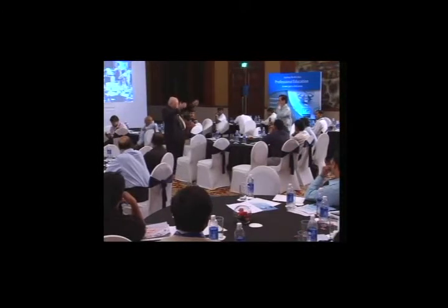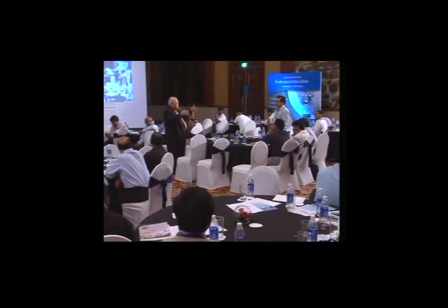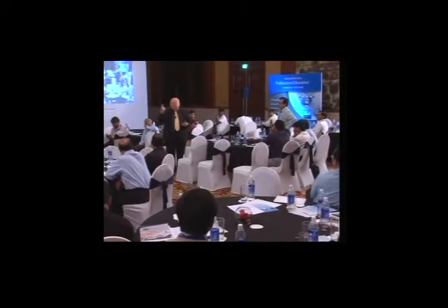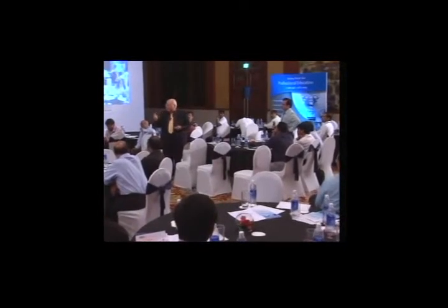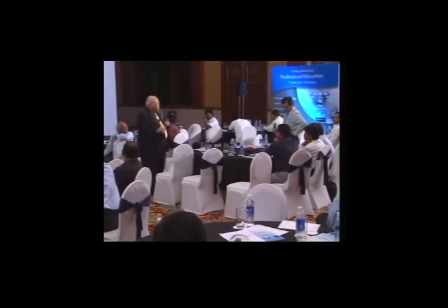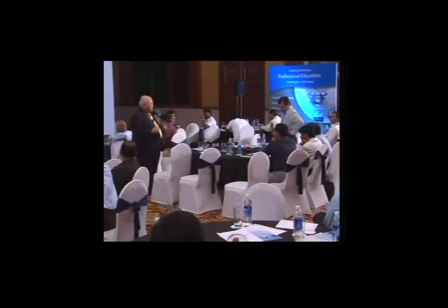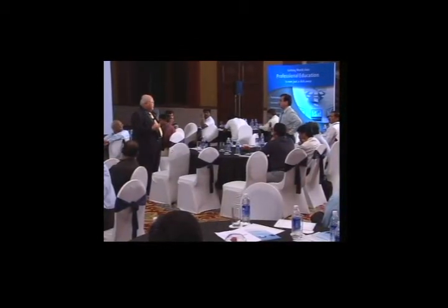Think of it this way. When you find that the original test had a problem due to an assignable cause, you've just invalidated that test. So when you do the retest, you're actually doing the first test. You're not doing a retest. That first test does not exist. So just follow your normal SOP.